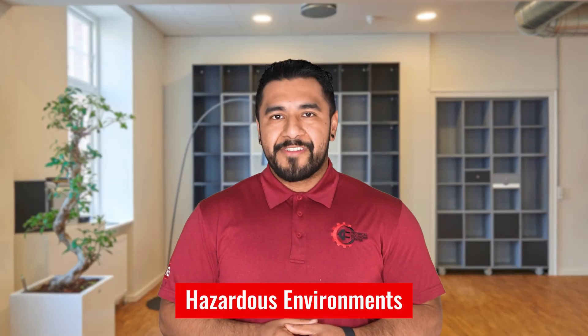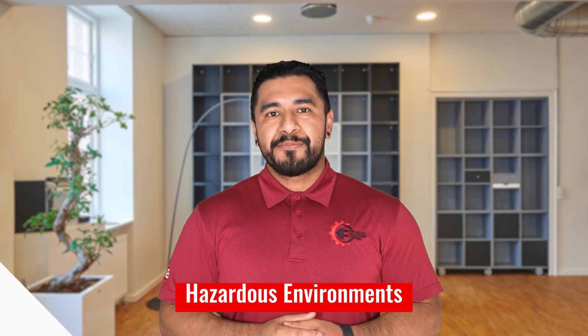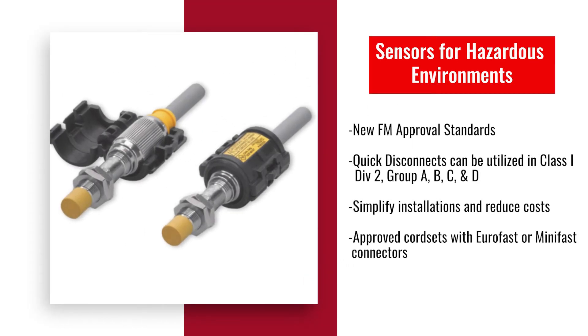If working in a hazardous environment, Turck also has you covered. With the new FM approval standards, quick disconnect sensors can now be utilized in Class 1, Div 2, Groups A, B, C, and D environments. This feature simplifies installation and reduces cost compared to traditional conduit methods. Turck also offers approved cord sets with EuroFast or MiniFast connectors for seamless integration.